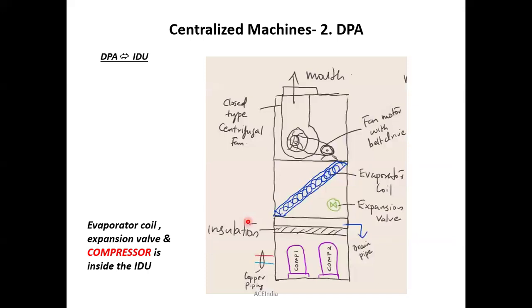Then, in the prior sessions, we studied that the copper pipe connection taken from the evaporator to the compressor is termed the suction line, isn't it? And from the condenser to the expansion valve, or even from ODU to IDU, is termed the liquid line. Why? Because it's going in a liquid manner, a liquid type, or a liquid phase. That's why it is called the liquid line. So here, do I need any suction line? No external suction line is required for this connection.